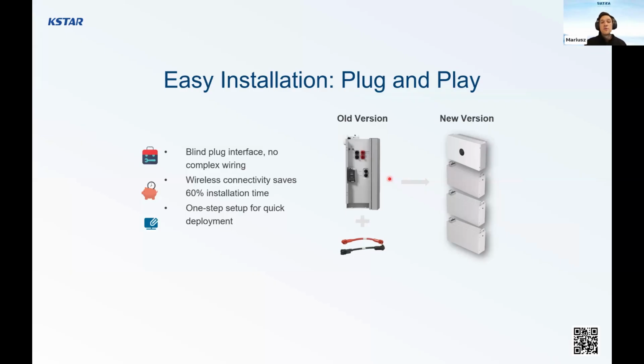Then you only have to think whether you will use up to 4 batteries or more than 4 batteries, because for up to 4 batteries, you are ordering just the batteries and the inverter. That's all. No wires, no communication wires, no additional BMS, no EPS box, nothing else. Just the battery and the inverter, because the floor stand is tightened up with the inverter as standard. So you receive the inverter, floor stand, and the batteries, and it's enough. For the solution with 5, 6, 7, or 8 batteries, you will need an additional floor stand, which will connect 2 stacks of the batteries.